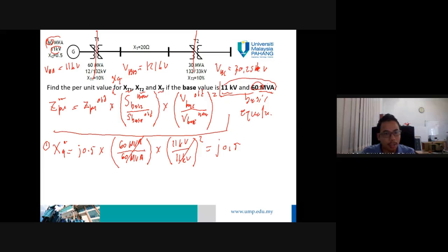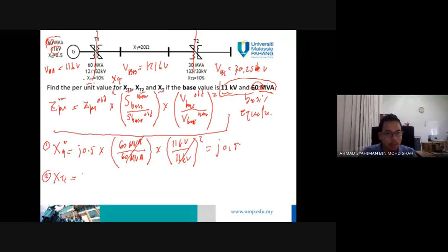Okay, what happens if I calculate next? XT1 means transformer 1 reactance. Okay, for transformer 1, the original per unit, S base all, is 10%. This 10% is equal to 0.1, remember. When we write 20% it means 0.2, 10% means 0.1. So J 0.1 multiply with S base new, 60 MVA, and the S base old, or original, is still the same, 60 MVA.